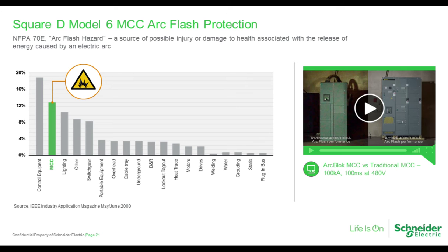Here is the IEEE research graph showing the sources of equipment in the distribution system causing injuries. As you can see, MCCs are the second highest source of the incidents. In the field, operators are more engaged with MCCs than any other low voltage distribution equipment. For that reason, we started our design with the Model 6 MCC, but this new innovative technology will be expanded to switchboards, panelboards, etc.